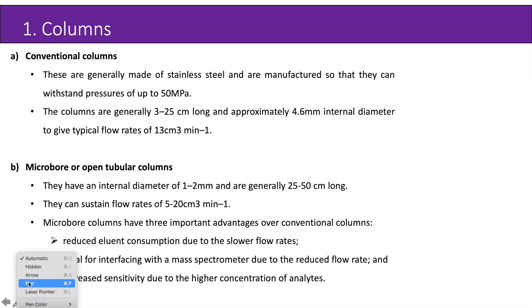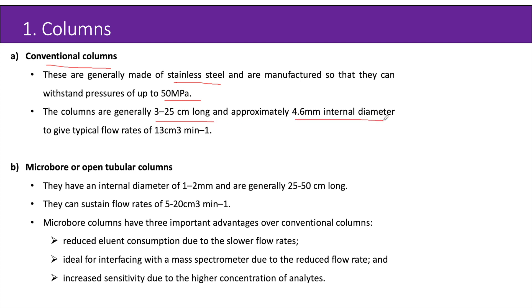Two different types of columns are majorly used for HPLC. First are conventional columns, generally made of stainless steel and manufactured to withstand pressures up to 50 MPa. The columns are generally 3–25 cm long and approximately 4.6 mm internal diameter, giving typical flow rates of 1–3 cm³ per minute. The second type is micro-bore or open tubular columns, with an internal diameter of 1–2 mm and generally 25–50 cm long, sustaining flow rates of 5–20 cm³ per minute.